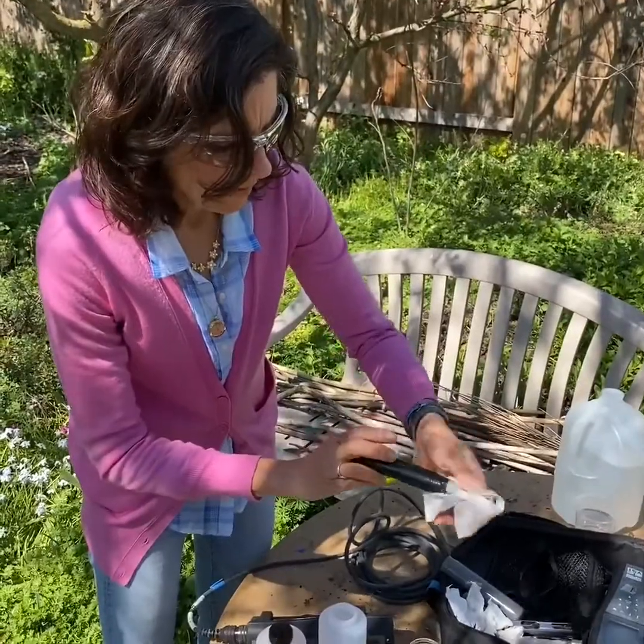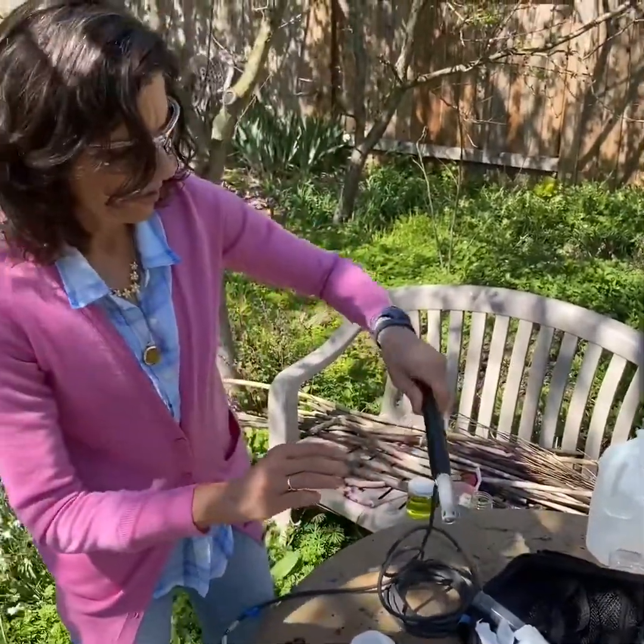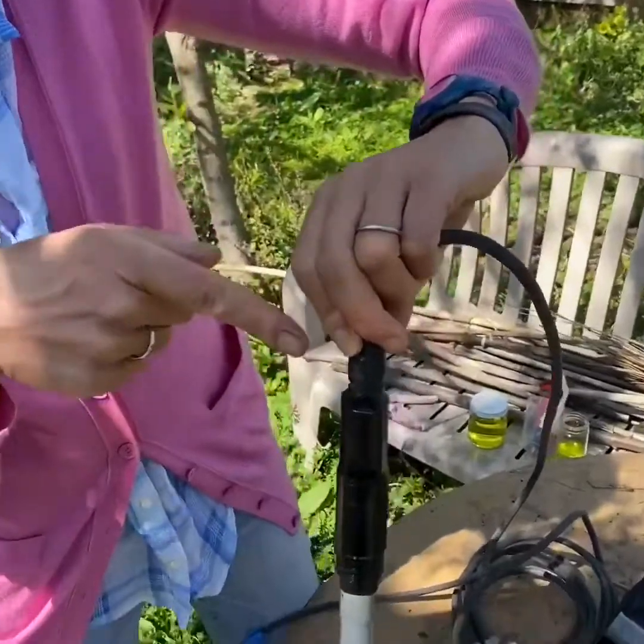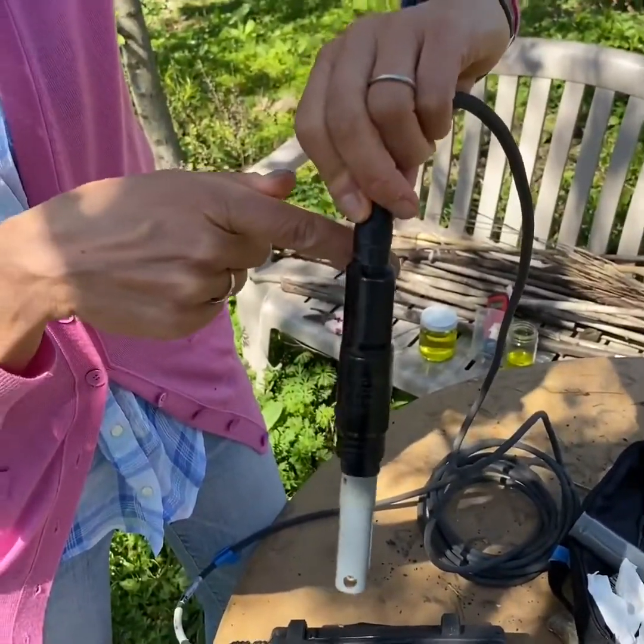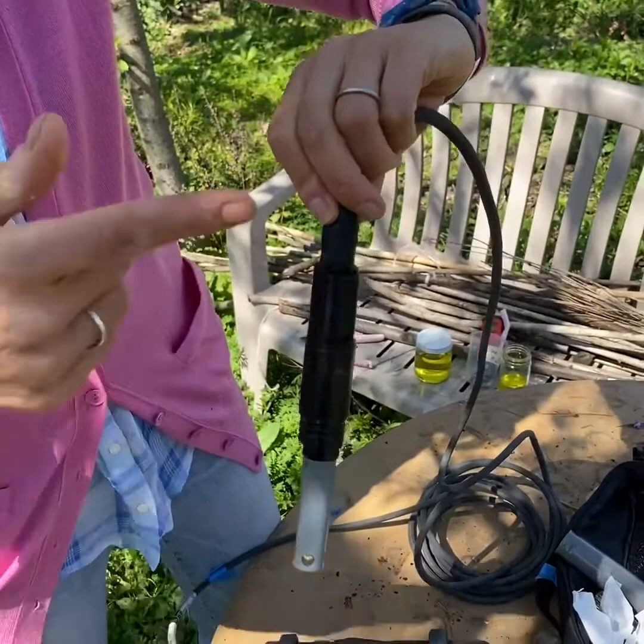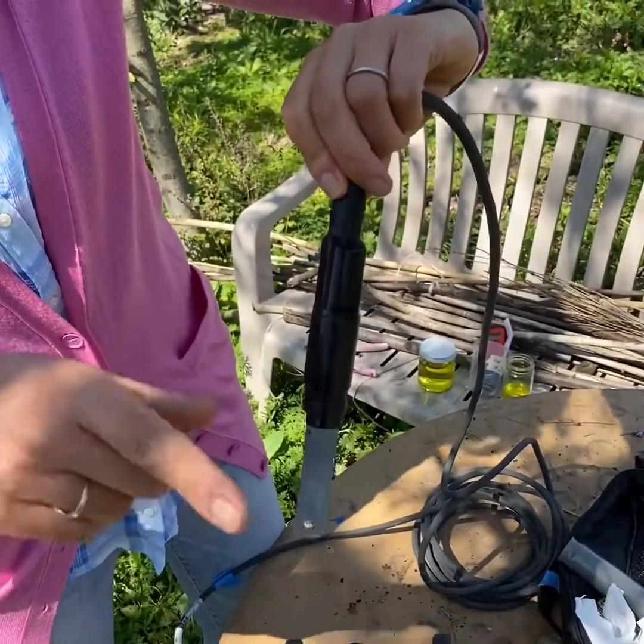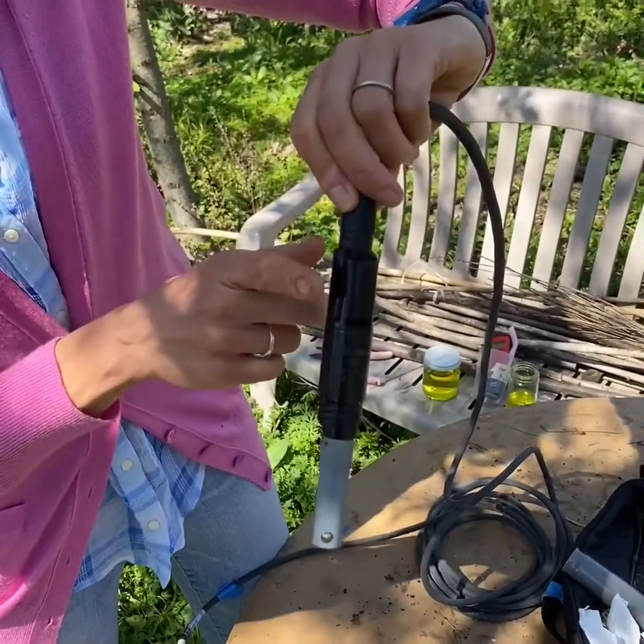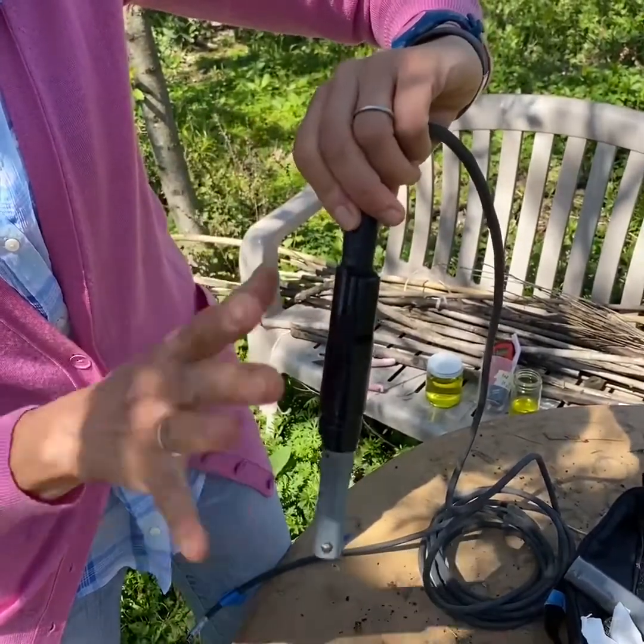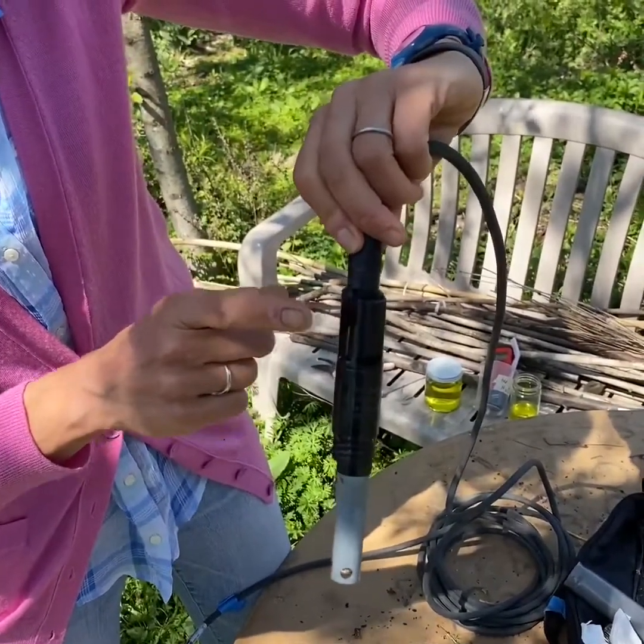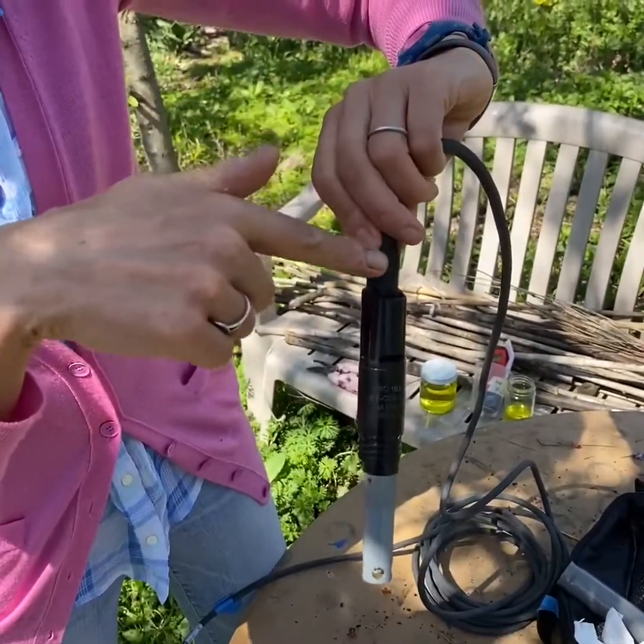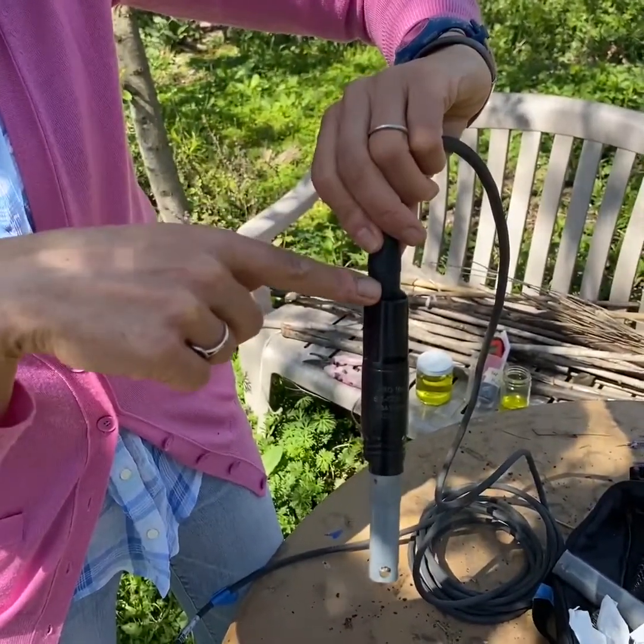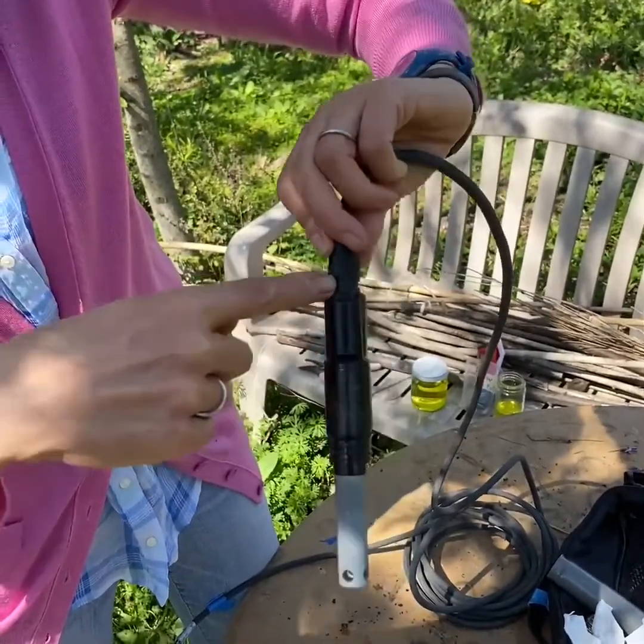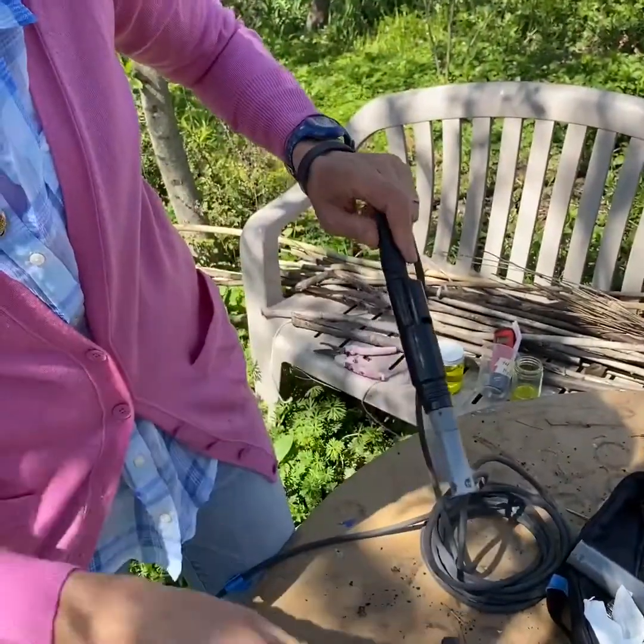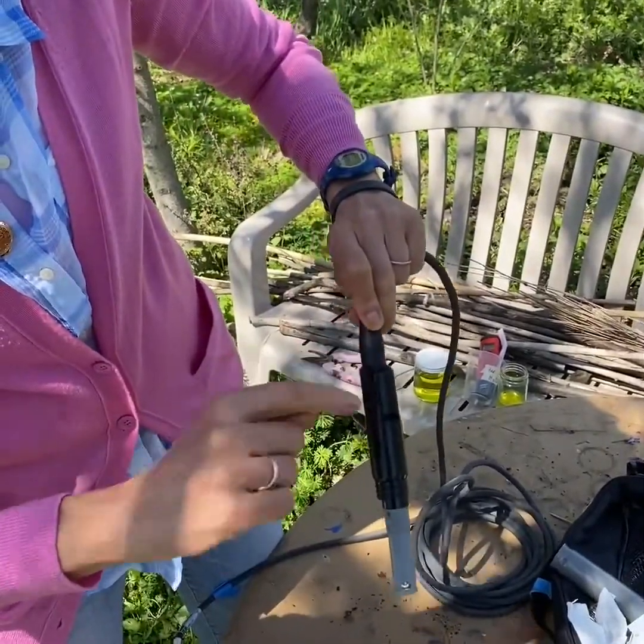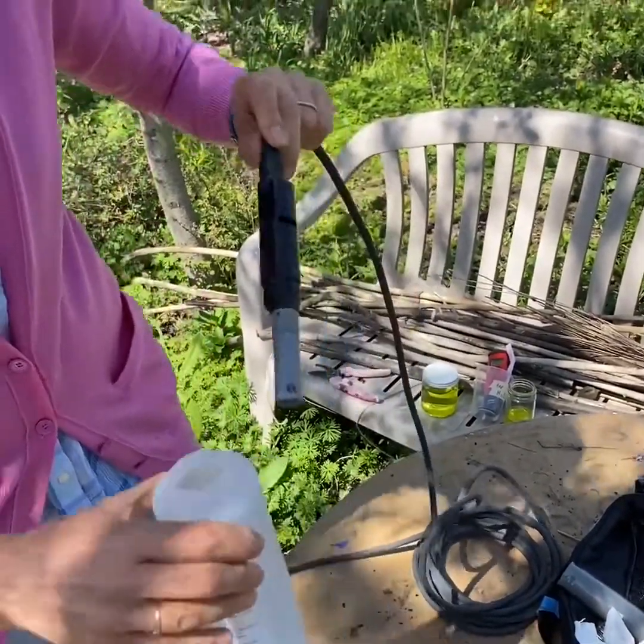And with this one, this is a very weird setup that they have. They have the EC meter way up here, and I think that's to keep it away from the pH meter, because the KCl that leaks from the pH meter can change readings of EC meters, so I think that's their way of separating it. But it's very inconvenient because you have to make sure you have it put into the water or the calibration solution deep enough to cover these two holes. So that's usually the big mistake that students make, is they don't put it in deep enough, because you think, why would I have to put it all the way in there?